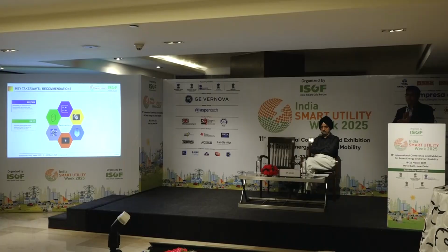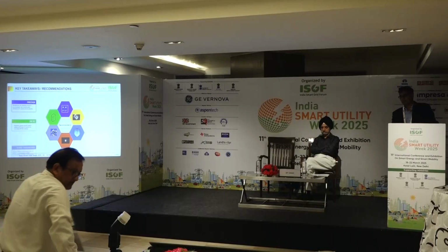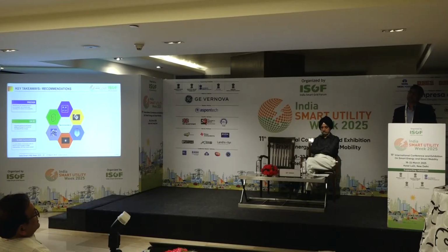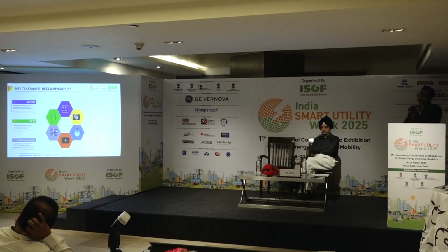But if we embed the function of DR data, disturbance recorder data, collection and analysis of the disturbance recorder data from the control center level is very essential nowadays. So with the same application, we need to embed the DRDC data concentrator option with the RTU and the station controller.